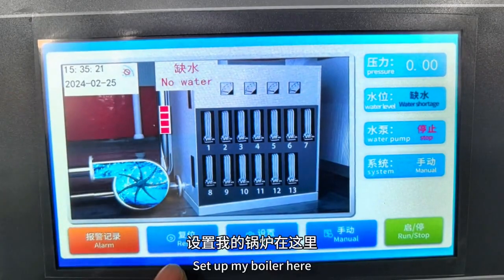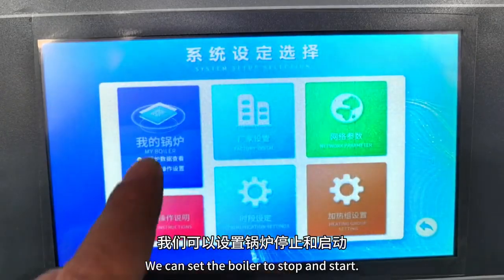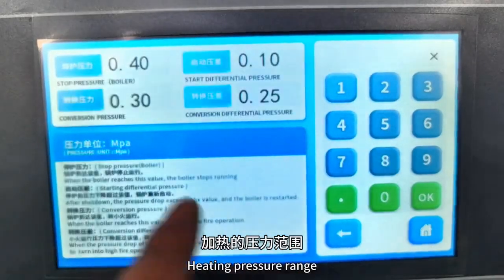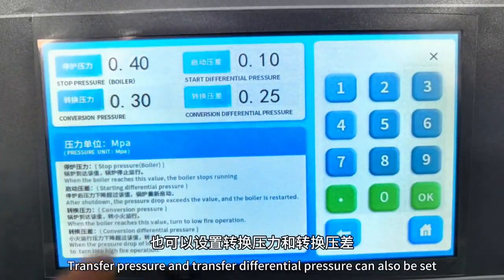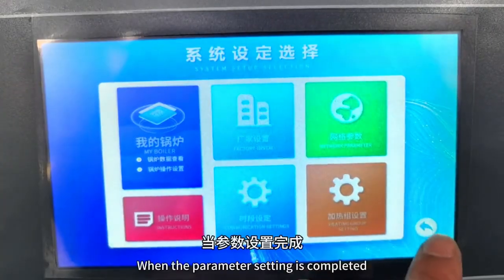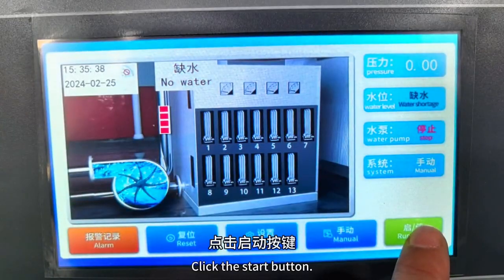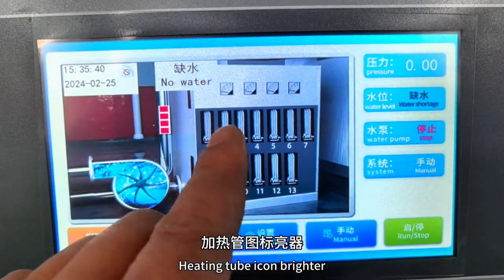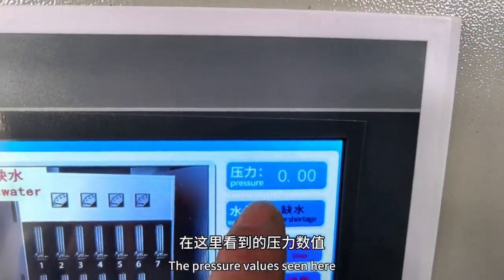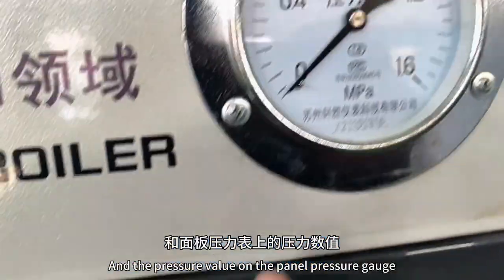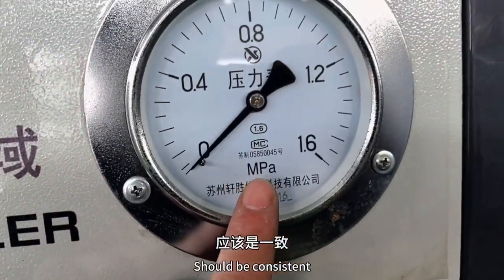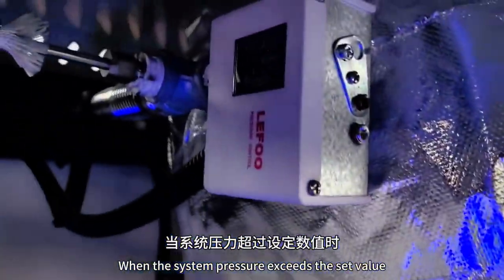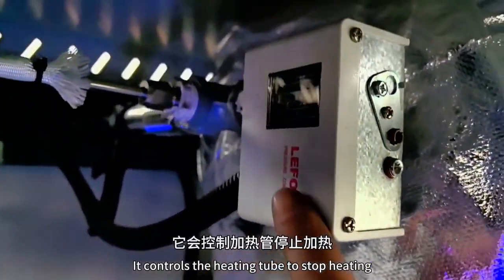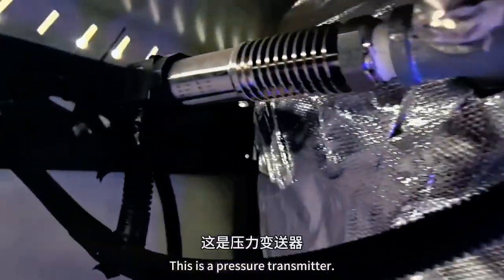Here, we can set the pressure range for the boiler to stop and start heating, as well as the conversion pressure and pressure difference. When the parameter settings are completed, click the start button to light up the heating tube icon, and the boiler starts heating. The pressure value seen here should be consistent or close to the pressure value on the panel pressure gauge. This is a pressure controller, which will control the heating tube to stop heating when the system pressure exceeds the set value. This is a pressure transmitter that constantly detects slight changes in system pressure and controls the start and stop of the heating tube based on the pressure.